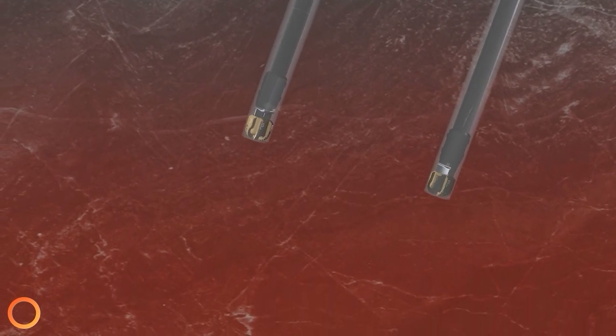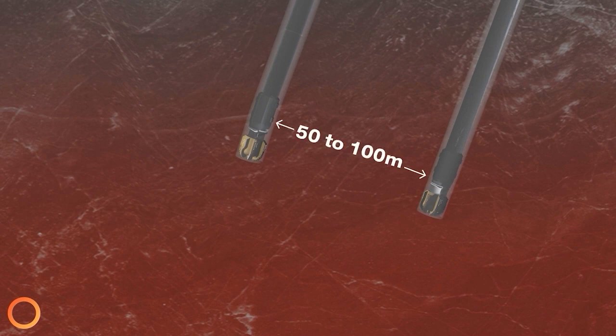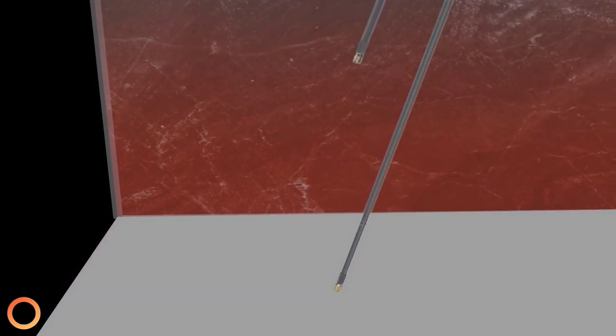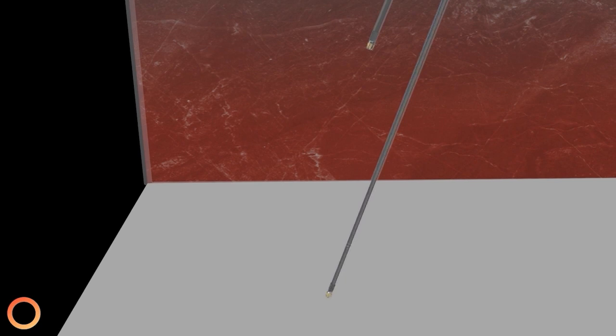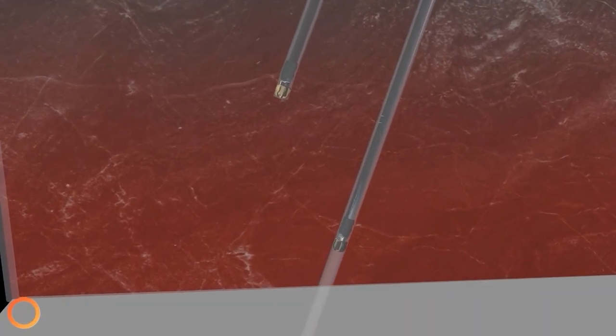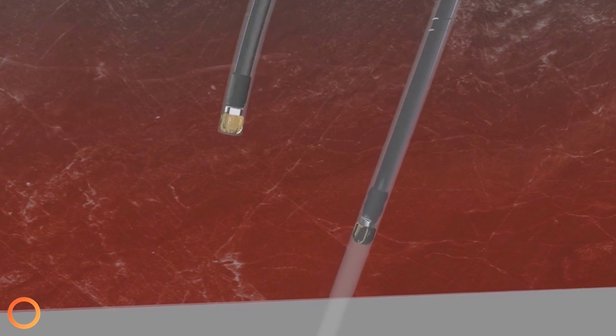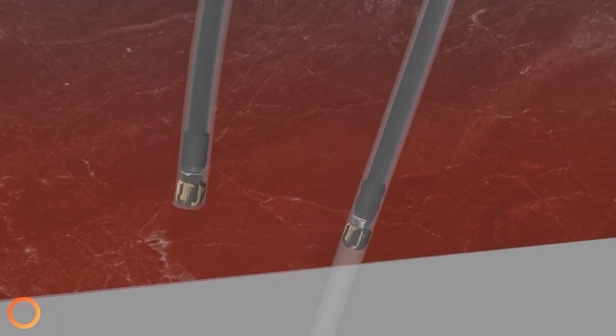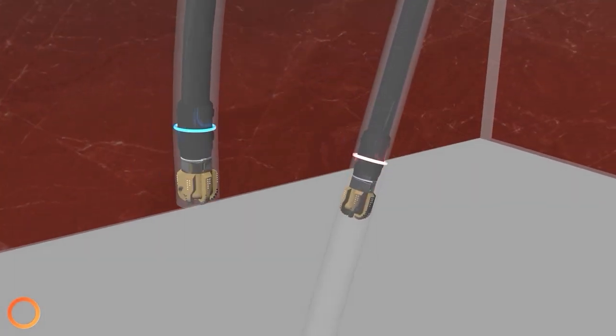In the process, you go down one vertical well, spread out, and slow down your fluid flow — which is just water — through that lateral section. Through conduction, you're soaking up the heat. You get to the end, do a bit of a U-turn, continuing to soak up heat into that same water, coming back the other direction, and then up the second vertical well to surface where you use the heat — through a heat exchanger to make electricity or for heat directly.